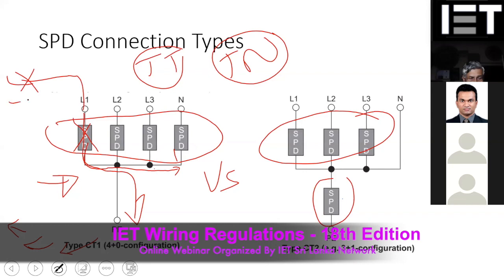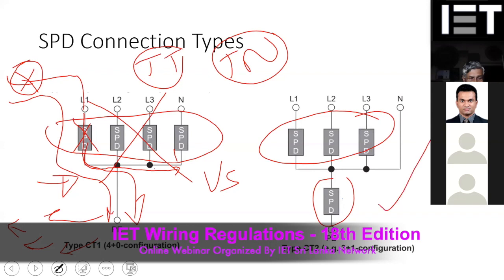Obviously not, because the leakage current is very small in a TT, as it will return through the ground. Our overcurrent protective device will not detect that type of fault, so there will be a sustained earth fault in the system, which our upstream overcurrent devices will not detect. Because of that, this arrangement is not recommended for TT, where you can go with this one. If there is a fault in one SPD here, you can see the fault will go like that.